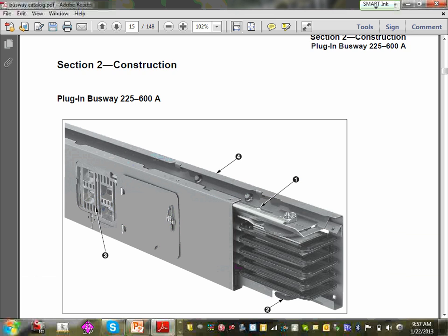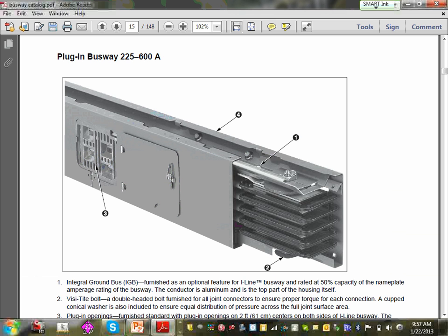Jerry, the frame is the equipment grounding conductor, right? Correct. Yeah, we use this frame as the ground. You don't need to pull an equipment grounding conductor or another box. It's a 50% ground. So you don't have to pull a separate ground, and when this unit plugs on, it makes the attachment and grounds itself, basically, so you've got a ground bar in here to attach.